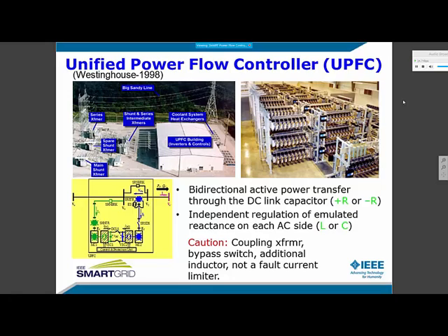Each series-connected inverter needs to have a coupling transformer, and the leakage reactance of the coupling transformer reduces the most useful rating, the capacitive rating, of the inverter. Although in theory the inverter can emulate an inductor, it is never designed to emulate a large enough inductor to limit a fault current. So, during a fault, the inverter is always bypassed, which requires a bypass switch.